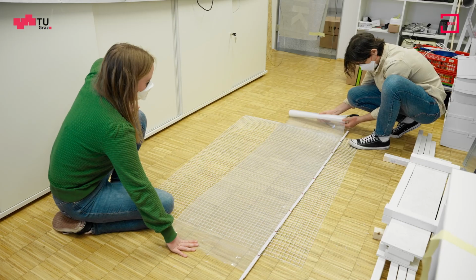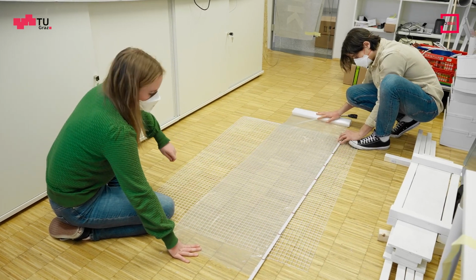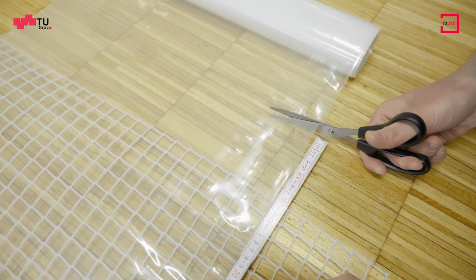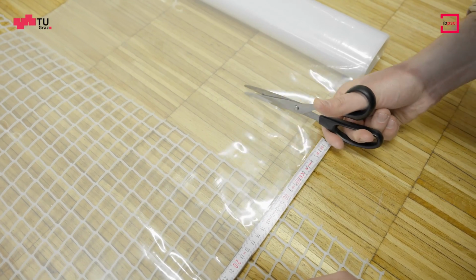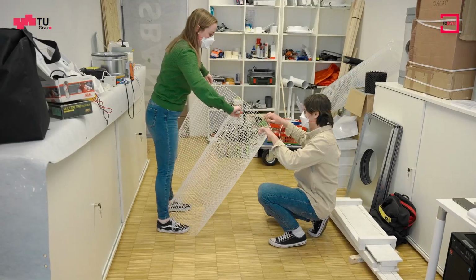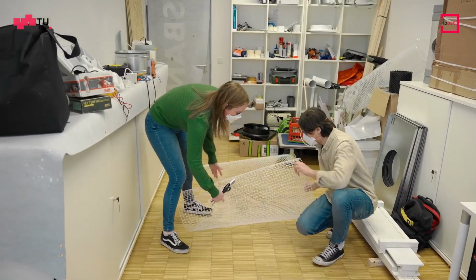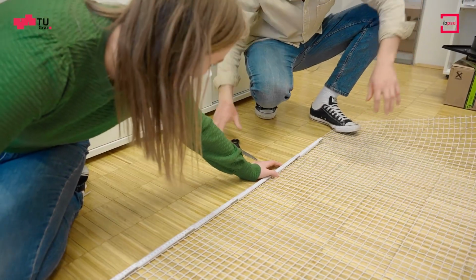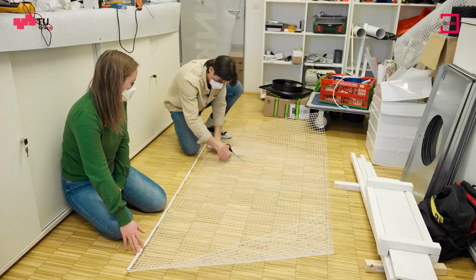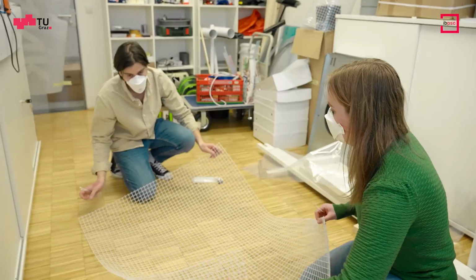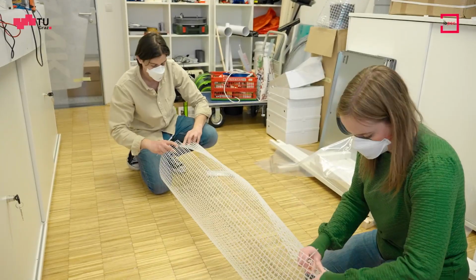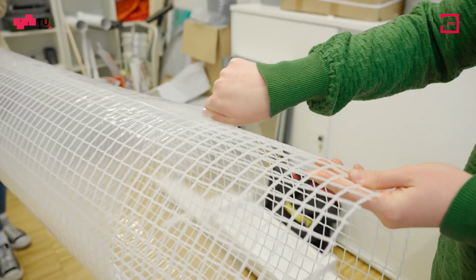The main ducts can be pre-made in sections before bringing them to the room. The main duct is formed in two layers. The outer layer is made from a clear polythene sleeve. The outer sleeve should be about 7 centimeters longer than the inner mesh, allowing it to overlap the connection pieces to which it is fixed. An inner layer made from a plastic mesh is formed into a 30 centimeter diameter cylinder in order to provide support for the outer sleeve.